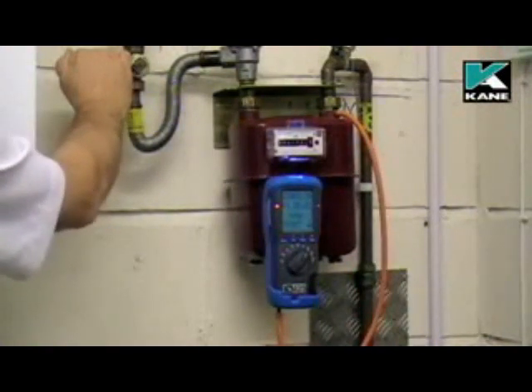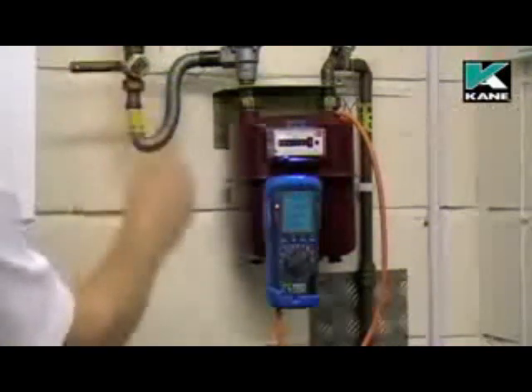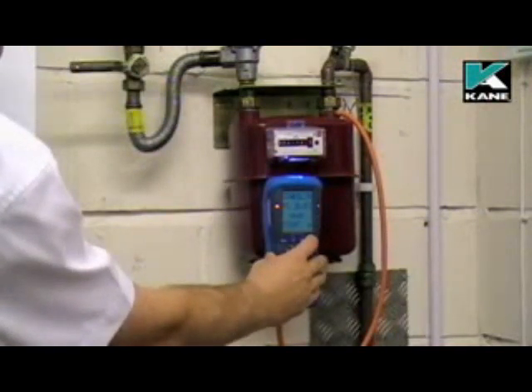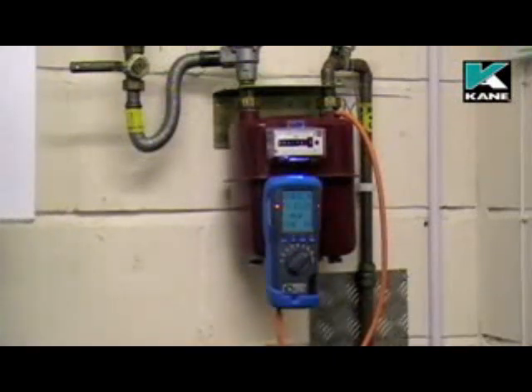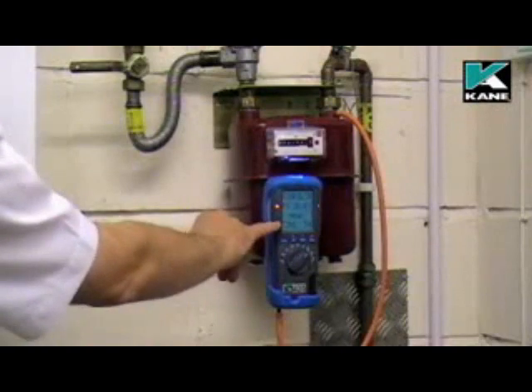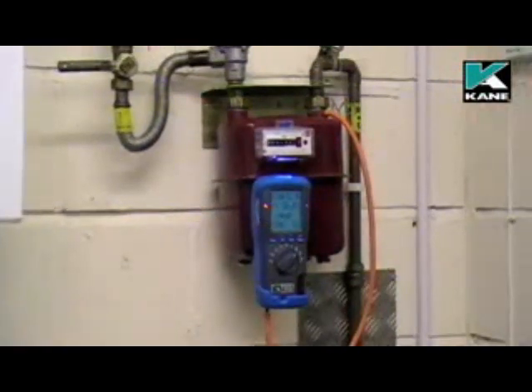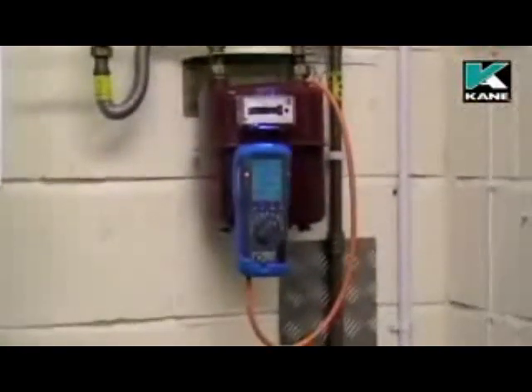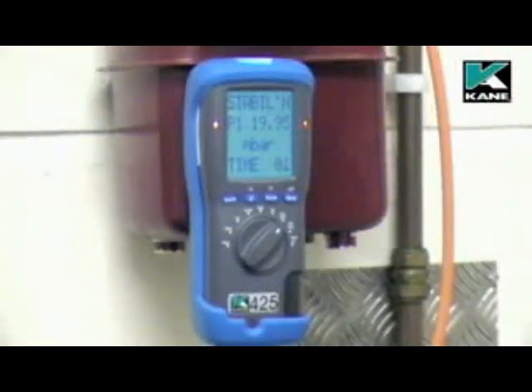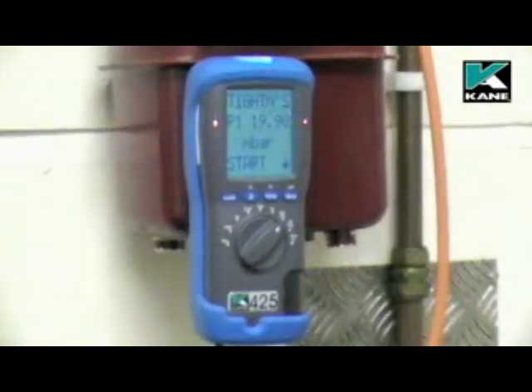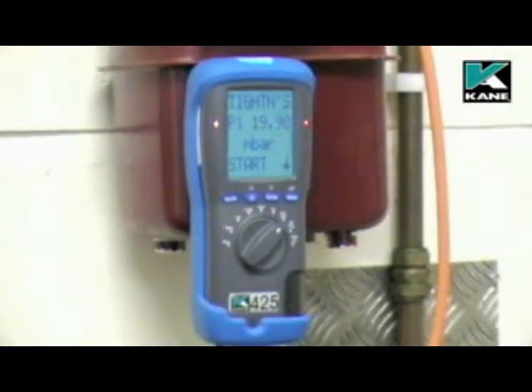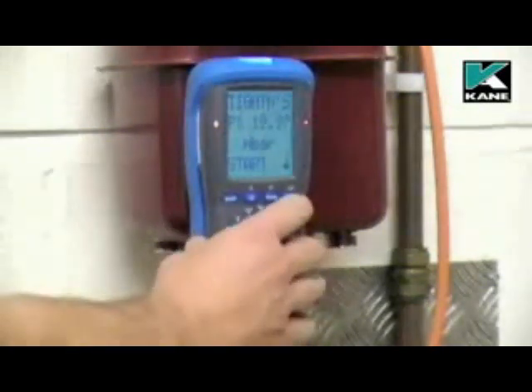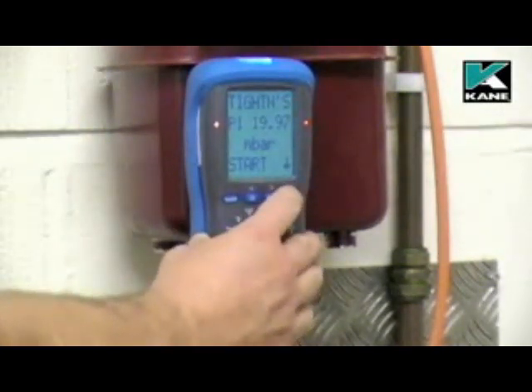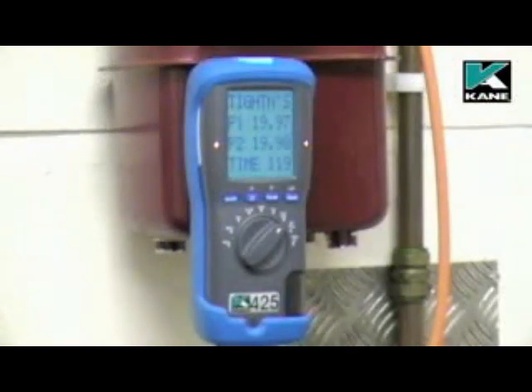When the stabilisation pressure has been set to 20 millibars, press the send button and the instrument automatically times the stabilisation for 1 minute. Again, this can be adjusted via the menu. When the stabilisation test has completed, press send to start the actual tightness test.